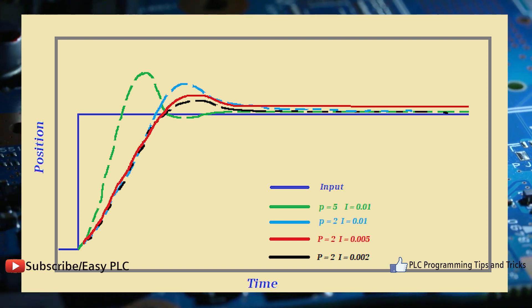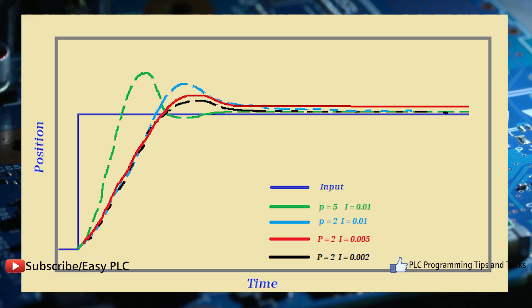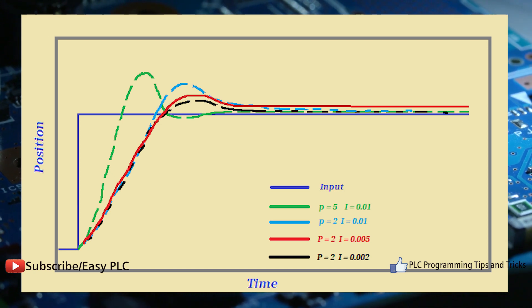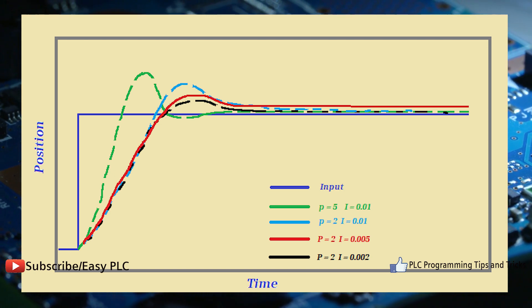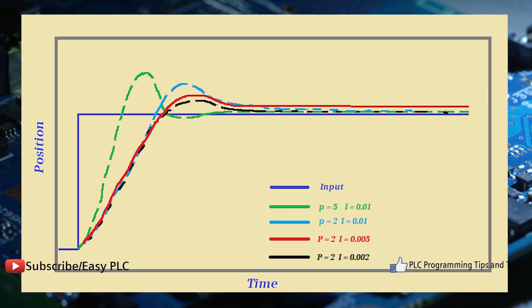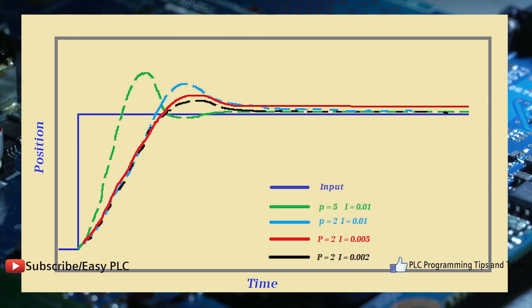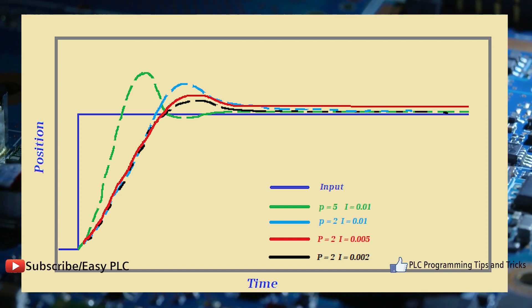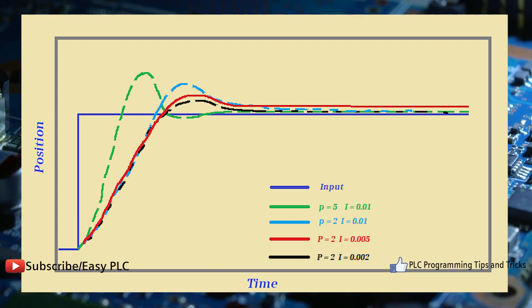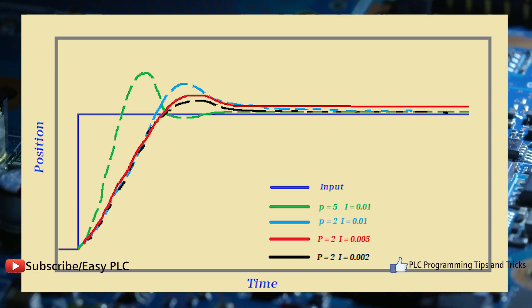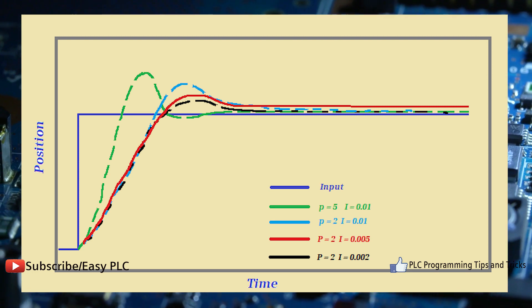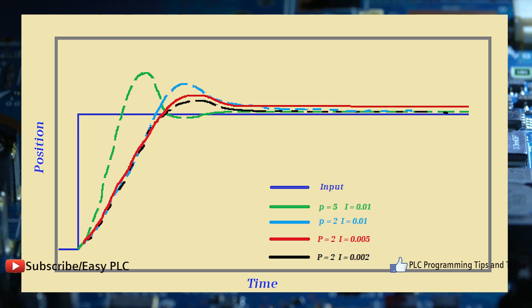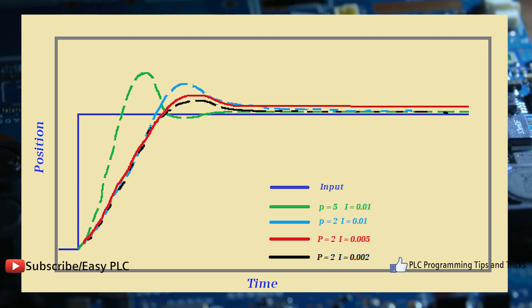For most of the cases, PI controller is used particularly where high speed response is not required. While using the PI controller, I controller output is limited to a certain range to overcome the integral wind-up conditions where integral output goes on increasing even at zero error state, due to nonlinearities in the plant.